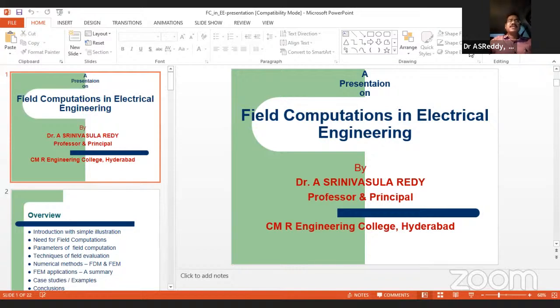The field variation, the field linkage to all those stray parts, is causing some losses. That loss is not accounted for in the conventional design. So this particular loss is causing, at times, some overheating or hot spot.